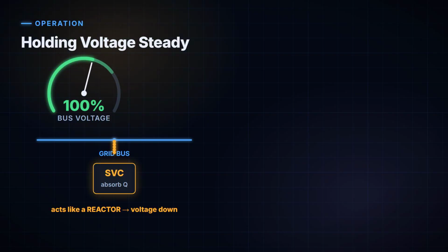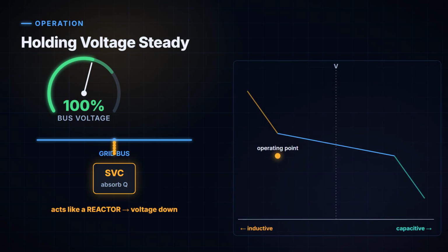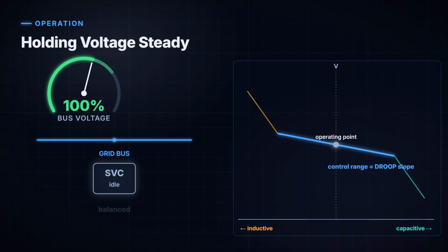We can summarize this entire behavior in one graph that every power engineer knows. Voltage on one axis, current on the other. In the middle, there's a gently sloped line. This is the control range, where the SVC smoothly trades between supplying and absorbing reactive power. That gentle slope, by the way, is deliberate. Engineers call it droop, and it lets several devices share the work without fighting each other. Push beyond the edges of that range, though, and the SVC simply runs out of capacitors or runs out of reactor. It's done all it can.